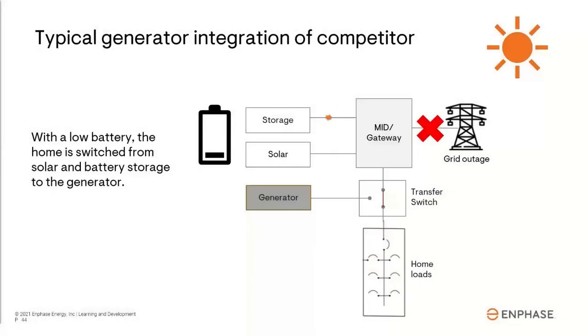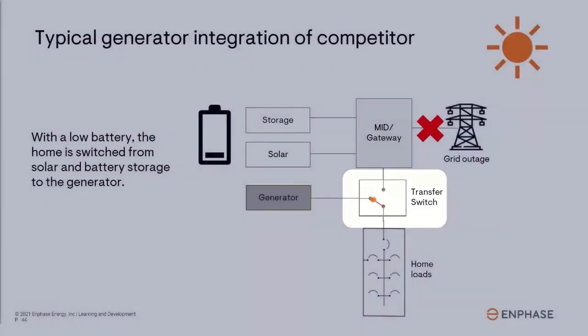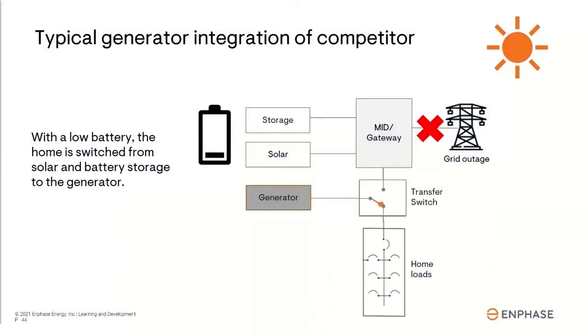Since it is coming out soon, I'm just going to review basically how it works again for those of you that are not familiar with it. First, I'd like to talk about how typical, non-Enphase systems work. Typical configurations use an external automatic transfer switch, and this allows either the solar and battery system or the generator to power the home, but they can't operate together at the same time. When the battery gets to a low state of charge, it'll switch the home's power source over to the generator, and then the solar and battery system will be off. And in some configurations from major manufacturers, you don't actually have the ability to go back to solar power the next day when the sun comes out. You're stuck using the generator until the utility grid comes back up.